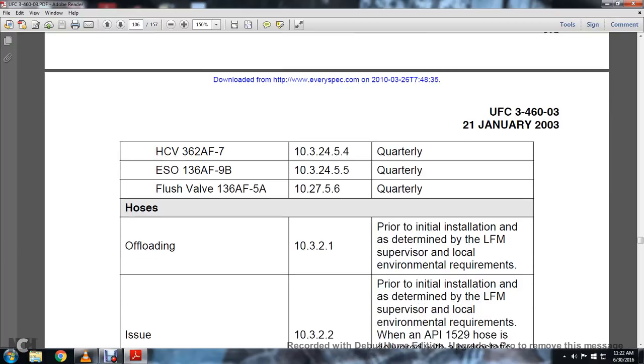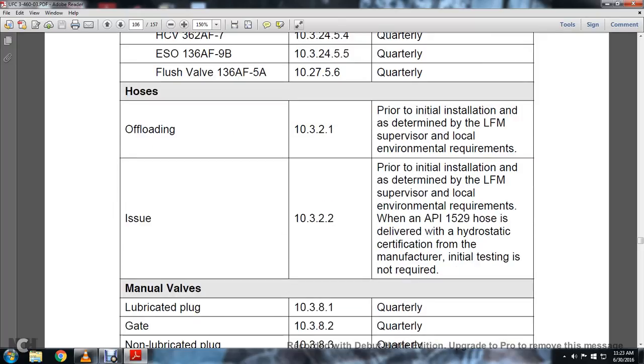All right, offloading hoses are in section 10.3.2.1. Prior to initial installation, testing is as determined by the liquid fuel farm supervisor and local environmental requirements. The hose issue is 10.3.2.2. Prior to installation, testing is as determined by the LFM supervisor and local environmental requirements. If an API 1529 hose is delivered with the hydrostatic certification from the manufacturer, initial testing prior to installation is not required.